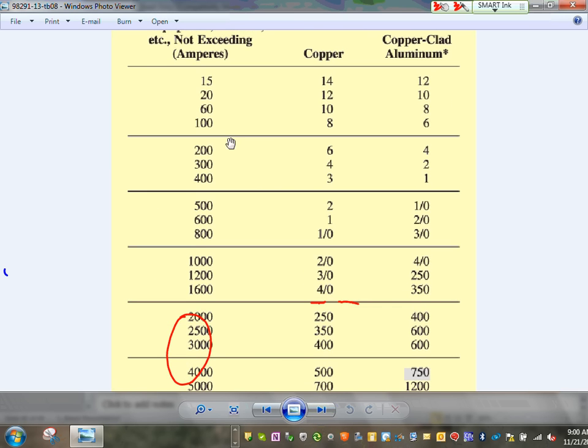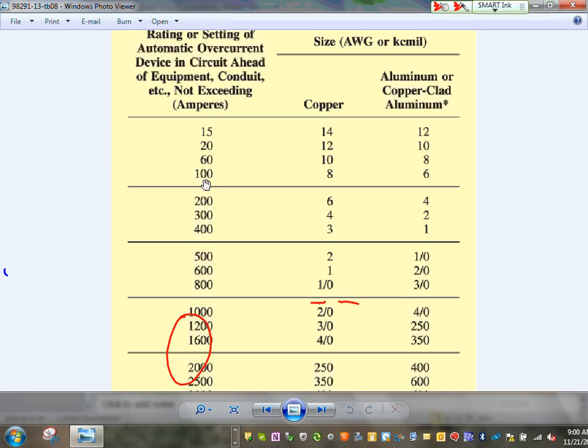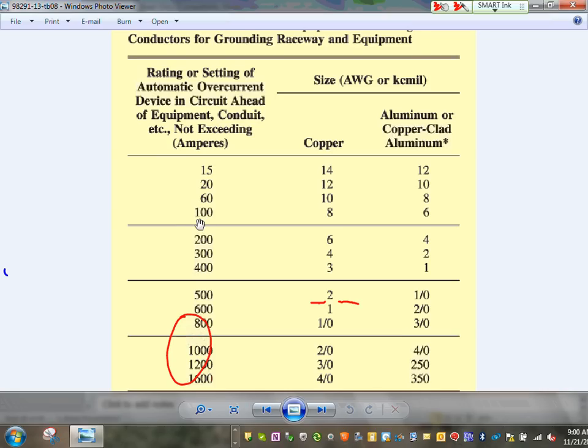Equipment grounding conductor, the 100 amp receptacle panel, if it wasn't fed with EMT and you need to pull a conductor, you have to pull a number 8 equipment grounding conductor with it. So there was a 125 lighting panel, or 200 amp panel. The 200 amp panel lighting, you need number 6 equipment ground conductor if it's not wired with an EMT conduit. Say if you put it with PVC. So that's the so-called equipment ground conductor.